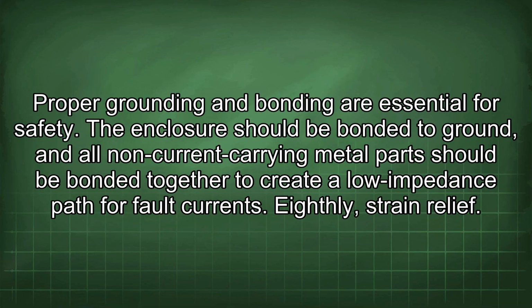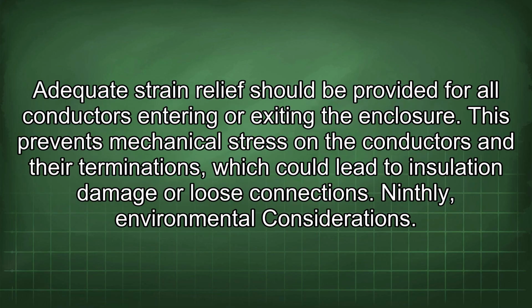Proper grounding and bonding are essential for safety. The enclosure should be bonded to ground, and all non-current carrying metal parts should be bonded together to create a low impedance path for fault currents. Eighthly, strain relief. Adequate strain relief should be provided for all conductors entering or exiting the enclosure. This prevents mechanical stress on the conductors and their terminations, which could lead to insulation damage or loose connections.